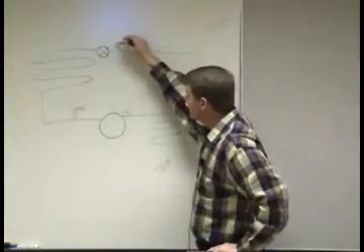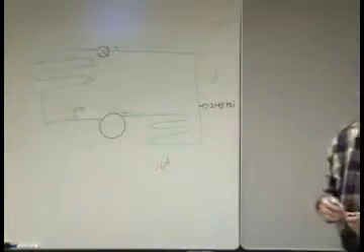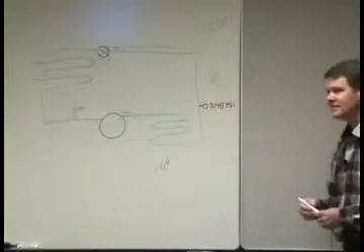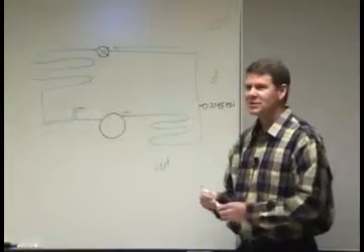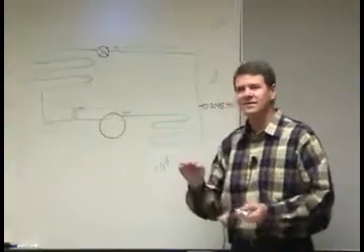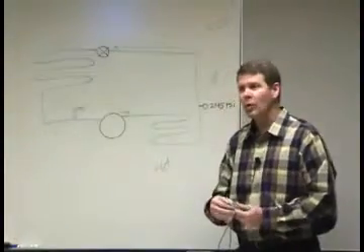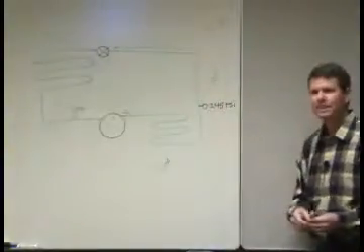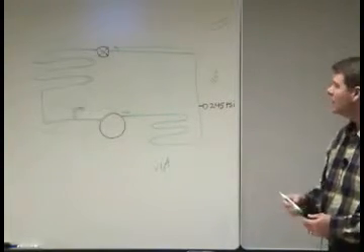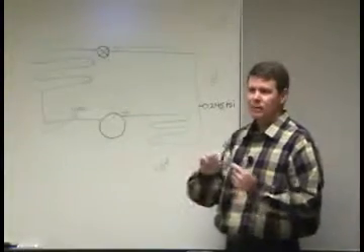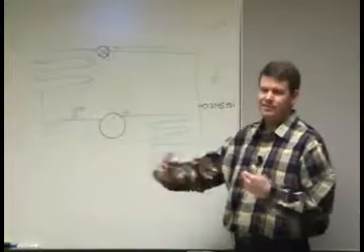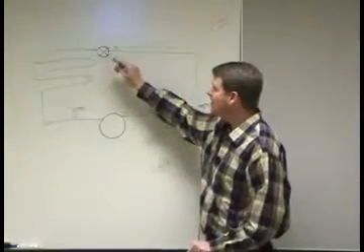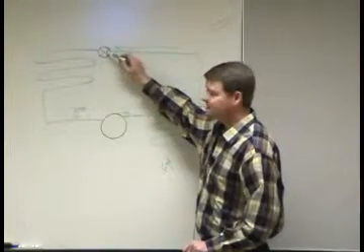This liquid comes up to this expansion device, which is down in your basement, right before it goes into the inside coil. Expansion devices have a lot of different varieties, and for the purpose of this discussion, we're not going to go into them a lot. Usually it's an orifice, or an expansion valve that measures what the temperature is going out, so it can exactly meter how much Freon goes through. But real common, they'll use a capillary tube, just a real fine piece of copper tube, so many feet long. Some clever engineer will decide how many feet long it needs to be to drop the pressure the amount they want. Just think of it as a restriction.